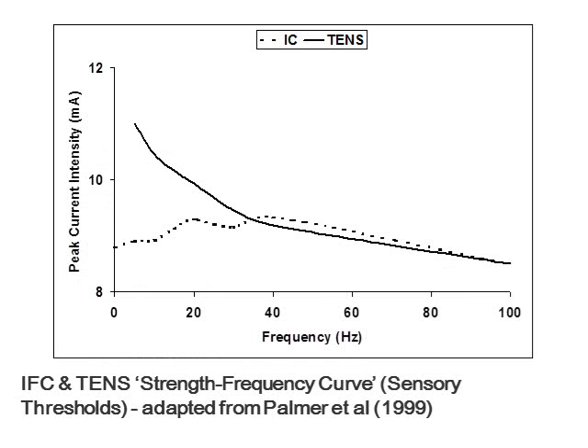This is shown in this graph. As TENS frequency decreases, it requires higher peak current intensities to reach sensory threshold. Alteration of the amplitude modulated frequency of interferential current, however, shows very little effect on the peak current intensity required, and a 0 Hz amplitude modulated frequency — i.e. pure 4000 Hz current — is similar to when an AMF is included. The medium frequency component of interferential current is therefore the most important component, rather than the AMF as traditionally claimed.